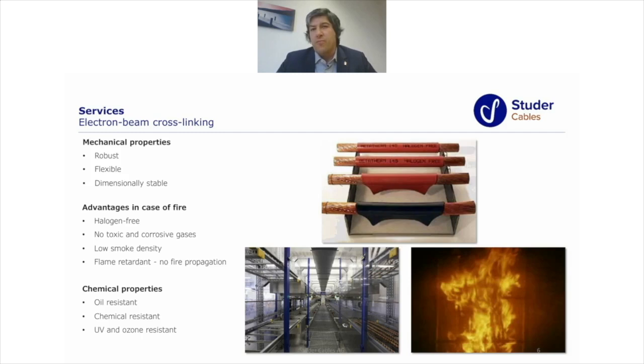The negative part is that the chemicals inside the cable remain there the whole time. This means the cross-linking process continues over time and creates more and more bonds between the polymeric structures, which at a certain moment turns from an advantage to a disadvantage. That means the cables or polymers become more brittle, more fragile.